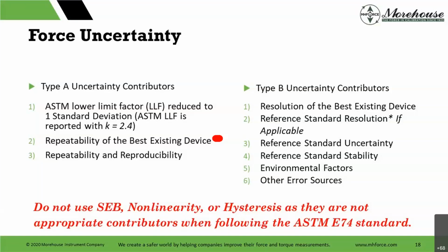Type B, resolution made its way back. Reference standard resolution, I say if applicable, because in force, dead weights do not have any indication system, so you're going to rely on what you're testing. Reference standard uncertainty, reference standard stability, environmental factors, and other error sources. Now, stability can be a type A or type B. There are some other things in there, but for the basics, typically we see stability as a type B, where you're comparing one calibration to the next.